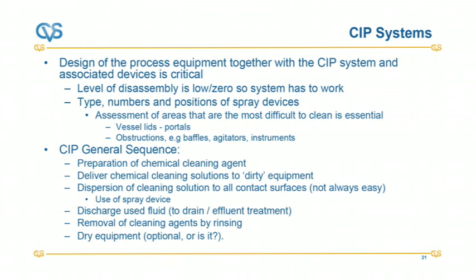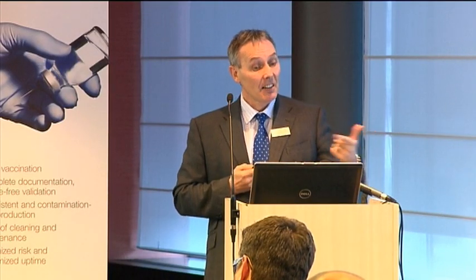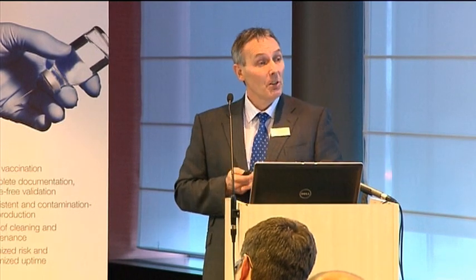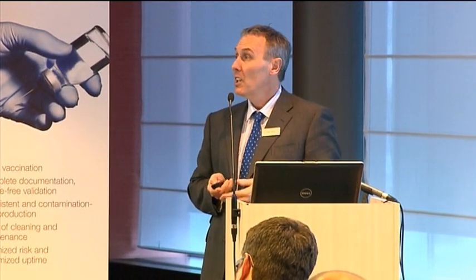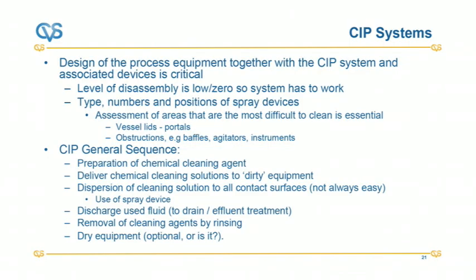And basically a general CIP sequence will involve preparation of the cleaning agents. That can be quite voluminous. It could be high temperature. It could have a lot of cleaning agents in. It could be quite costly. Then delivering of that chemical to the dirty equipment. So we want to get full coverage to make sure it cleans. So making sure that we get everywhere is not always easy. So this is where the design and type of spray device is quite critical. Then we just need to discharge that used fluid to drain.